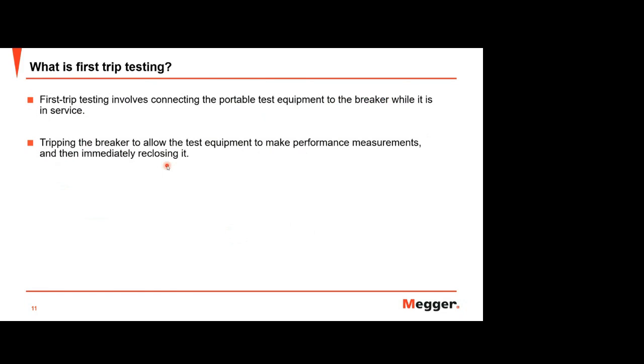So it is not totally de-energized. We try to trip your system, and after that you can reclose it again. So you don't need to take longer time as in conventional maintenance testing, but you just take a few minutes and then the system will run as normal again. This is the first trip testing.